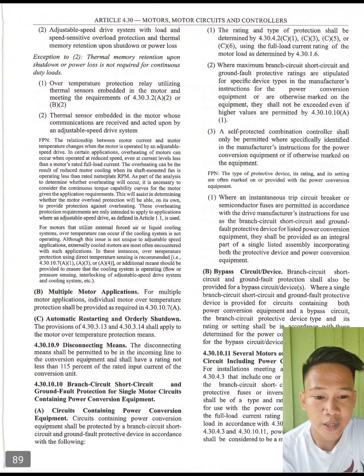Third, overload protection relay utilizing thermal sensors embedded in the motor and meeting the requirements of 4.30.3.2 A2 or B2. Fourth, thermal sensor embedded in the motor whose communications are received and acted upon by an adjustable speed drive system. So B, multiple motor applications. For multiple motor applications, individual motor over temperature protection shall be provided as required in 4.30.10.7a. C. Automatic restarting and orderly shutdown. The provisions of 4.30.3.13 and 4.30.3.14 shall apply to the motor over temperature protection means.